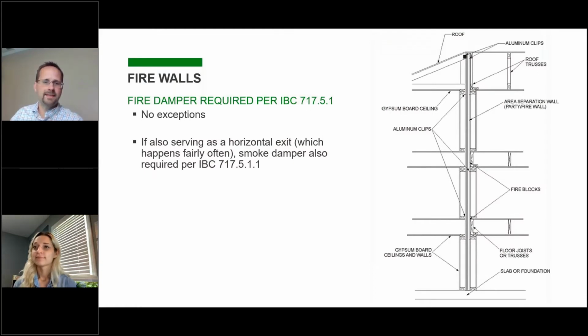So as far as dampers and firewalls, it's a lot simpler. A true firewall is much simpler than other walls and assemblies because there aren't that many exceptions. Basically, you need a fire damper when you penetrate a firewall. No ifs, ands, or buts. There are a few caveats. If a firewall is also serving as a horizontal exit, you would need a smoke damper and a fire damper, so you'd have a fire smoke damper in the assembly.